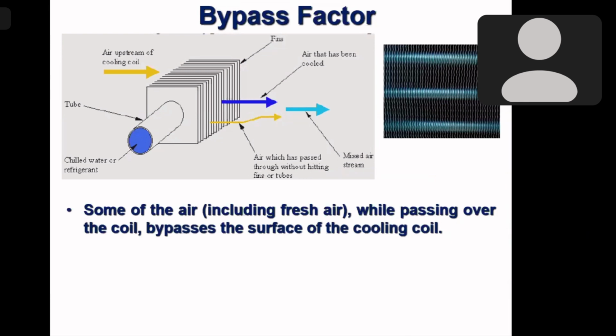The mixture of return air and outdoor air, we pass over the cooling coil. How does the cooling coil look? It has copper tubes, and over the tubes we have aluminum fins stacked at very close intervals, say 10 to 14 fins per inch length. On the right-hand side, you see the actual photograph of a cooling coil, where you have the copper tube, and over it there are fins. The fins are a little corrugated in shape like this, and the air flows over them.